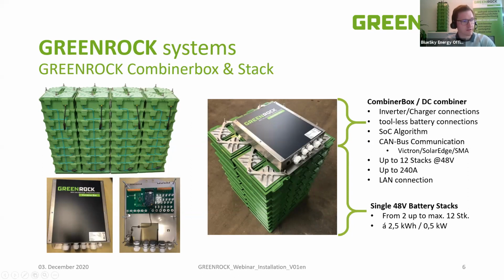Also inside the box, you can see here in the middle the connections for the inverters. For example, if you want to use your own 48-volt inverters, most of the time you can use them, but you have to adjust the charge curve. That's really important. There's an instruction manual you can download from our partner portal, so this is really important if you do such things.